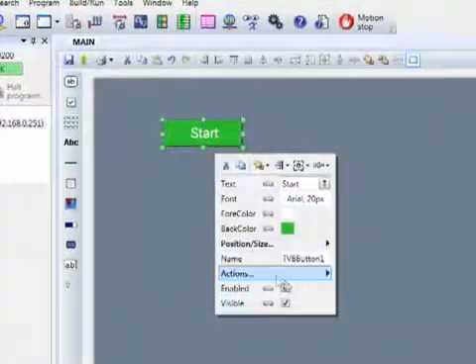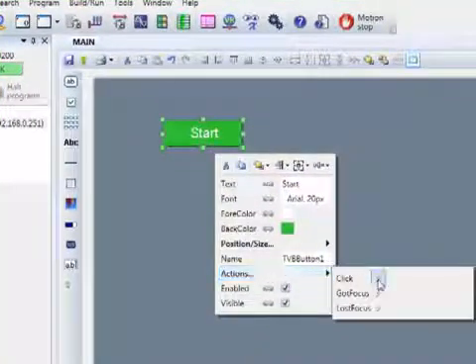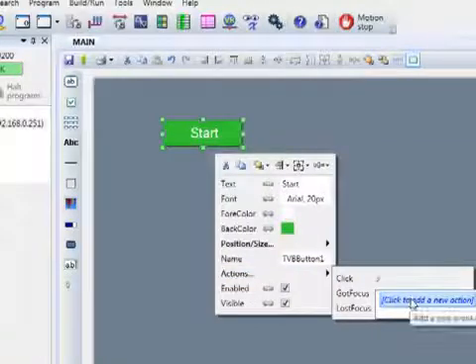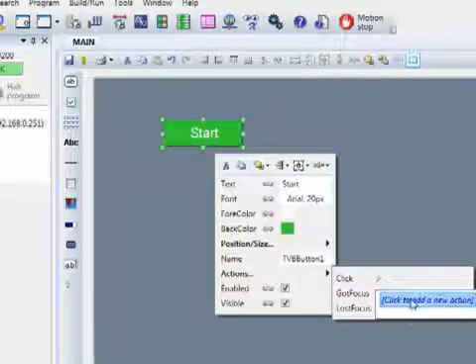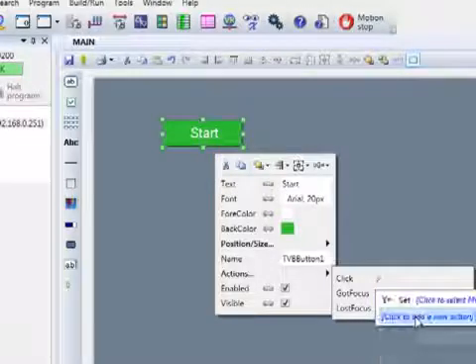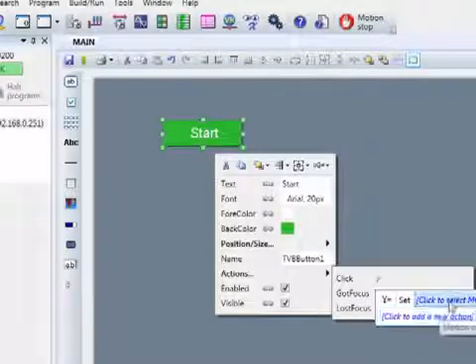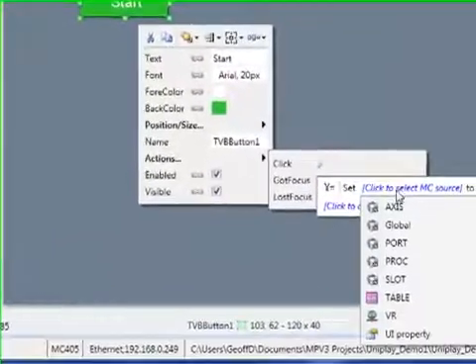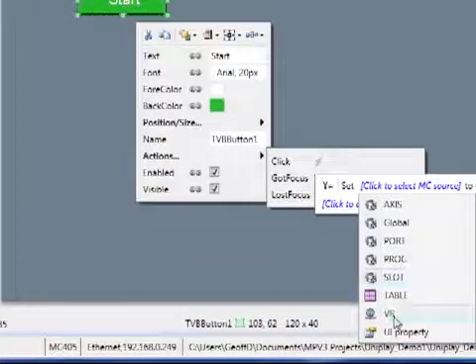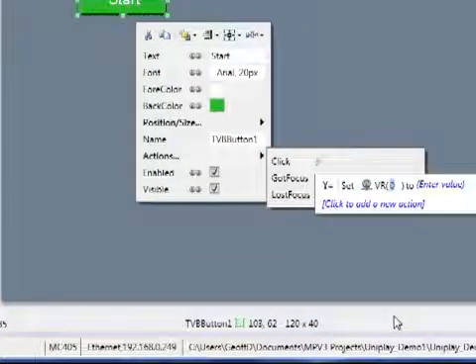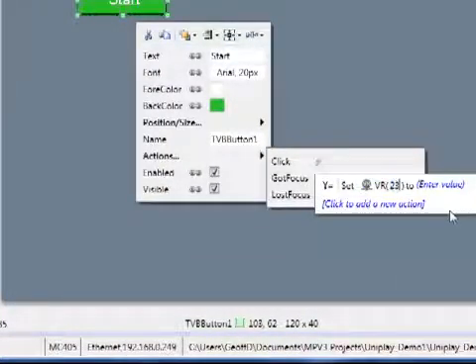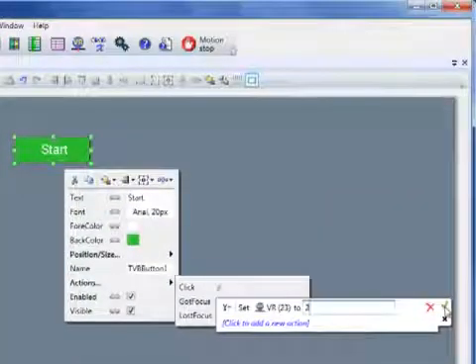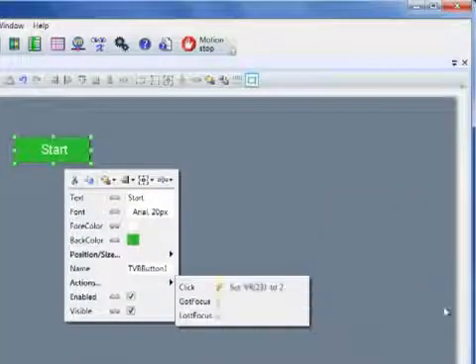I can give the button an action within the Motion Controller. So here we're going to on-click add the action to set a variable, and we'll choose a global VR variable in the Motion Coordinator, say variable 23, and when we click the button we'll set it to 2, which will mean Start.